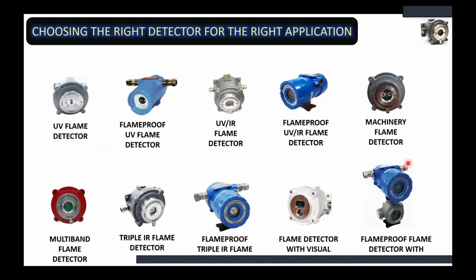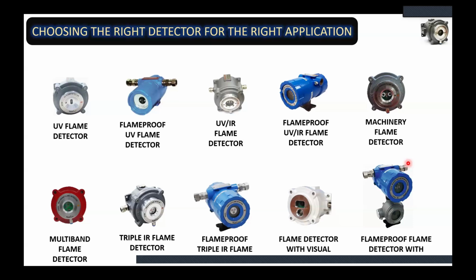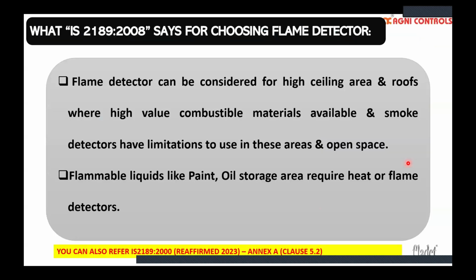So even though the flame detector is the quickest method of detecting the flaming fire, the suitable detector has to be chosen for the right application. There are different types of flame detectors available, and the designer must be very sure in choosing the right detector for the right application. So again, coming back to IS 2189, it can be considered for high ceiling areas, roofs where high value combustible materials are available, and where smoke detectors have limitations, and open spaces. Flammable liquids like paint and oil storage areas require heat or flame detectors. So this is what the standard suggests.